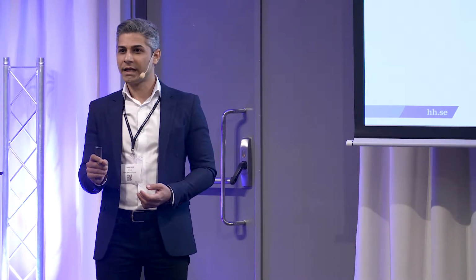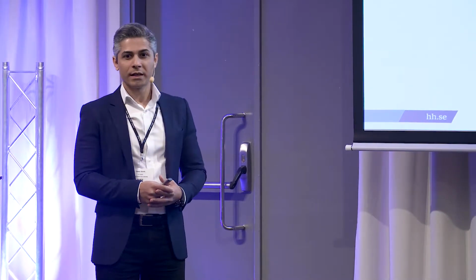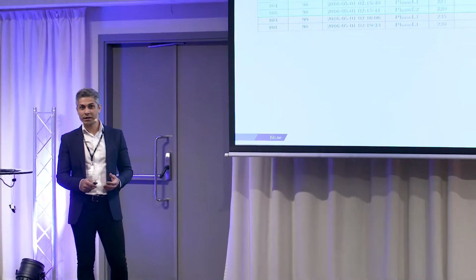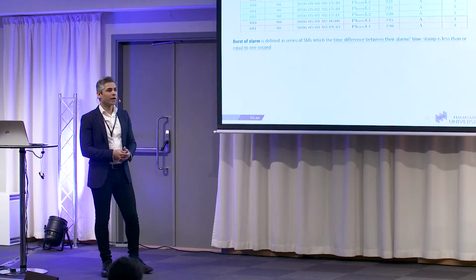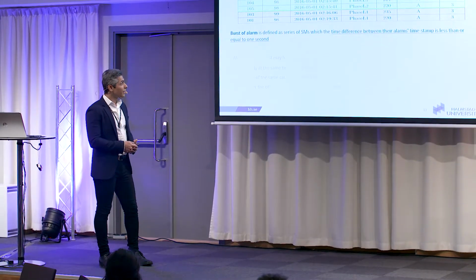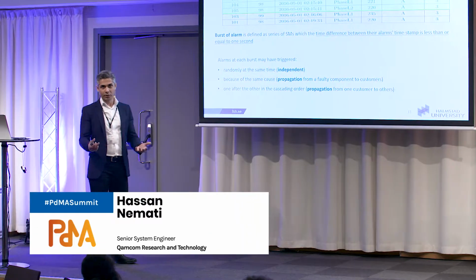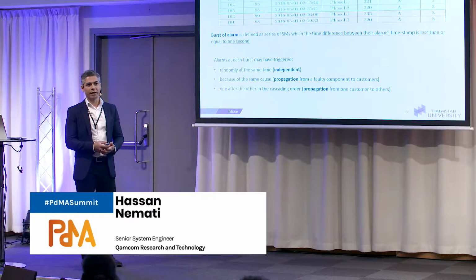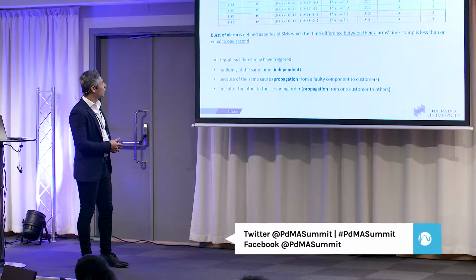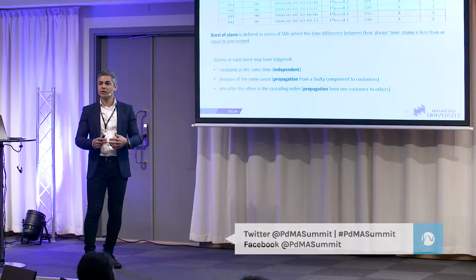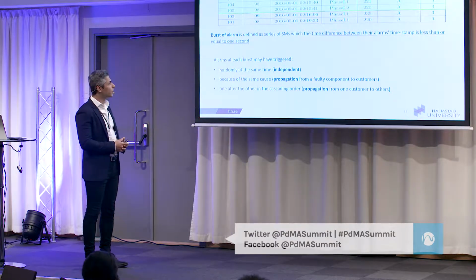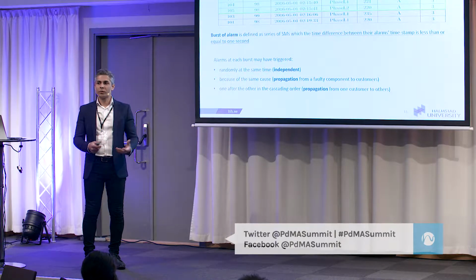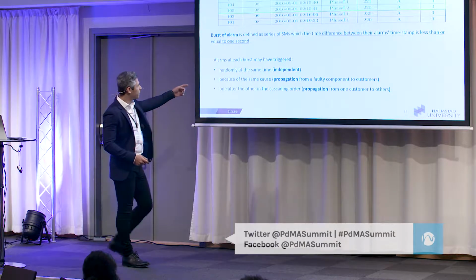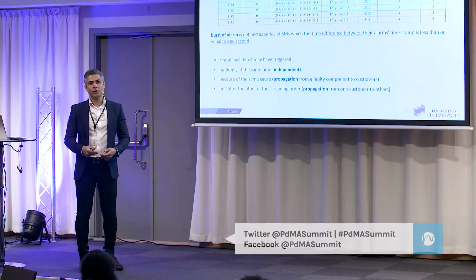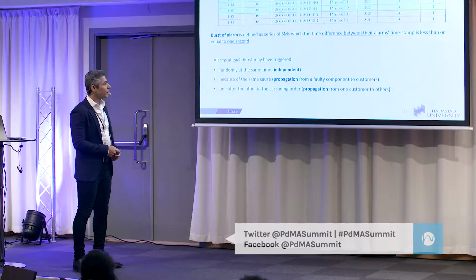The data look like this, and because the precision of the alarms is 1 second, we join together the input data whose time difference is less than or equal to 1 second, and we create a burst of alarms from this data. Then we looked at these bursts, and we have 3 different general situations. These alarms from different smart meters may happen just randomly together at the same time, or there could be a problem in the grid that causes this alarm in all of the smart meters connected to that part of the grid, or it could be a customer generating the alarm and it propagated to other customers. So except the first one, the other two are important for the company in order to strengthen the grid and avoid power quality problems for other customers.